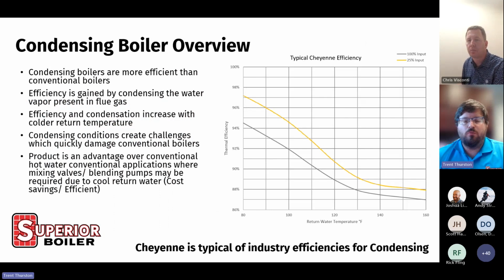So just a general review of what a condensing boiler is. They are more efficient than conventional boilers. That is why you will pick a condensing boiler. It gains this efficiency by condensing the water vapor in the flue gas. When you burn natural gas, depending on operation, it'll be about 13 to 18% water vapor in the flue gas, and we condense this to gain our efficiency.